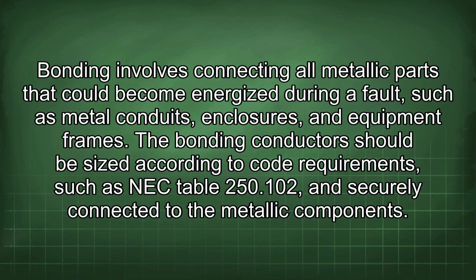Bonding involves connecting all metallic parts that could become energized during a fault, such as metal conduits, enclosures, and equipment frames. The bonding conductors should be sized according to code requirements, such as NEC Table 250.102, and securely connected to the metallic components.